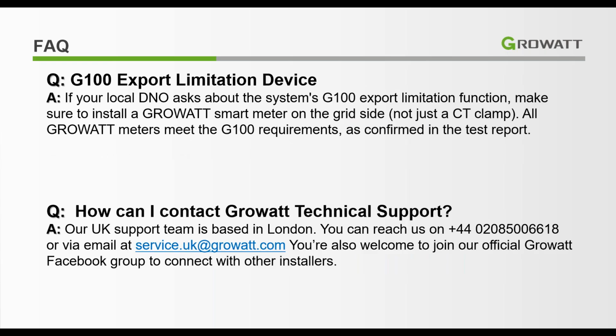And then finally, the G100 export limitation device. The DNO has just realized that export limiting is the most important thing now, so they're being very serious about G100. We have the test report, everything has been submitted on the ENA, so just go check the test reports. Also just add a meter like I mentioned before - all our Growatt meters that come with the system will have the G100 export limitation function. Once you have the meters, just enable the export limiting function and you'll be able to see it, or you can go check the test reports. There are a few meter selections, but all of them are from Growatt, so that's no problem.